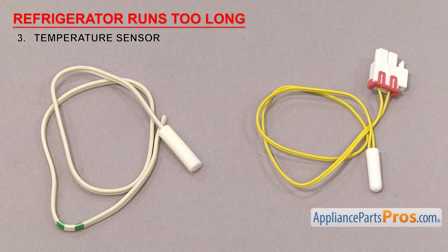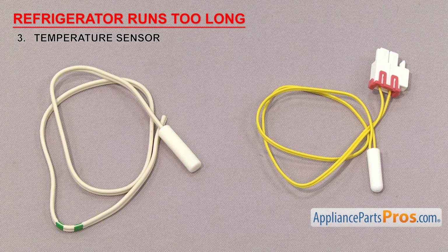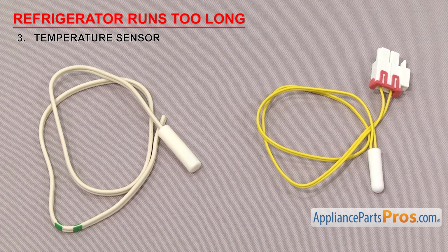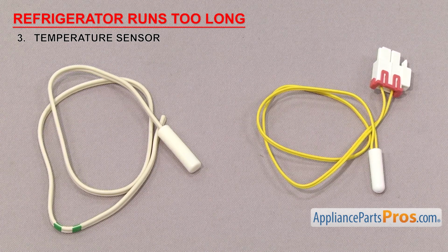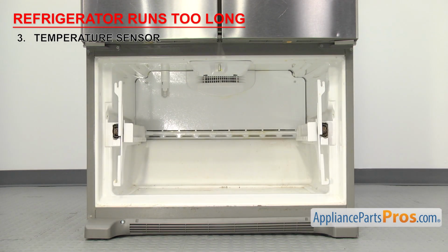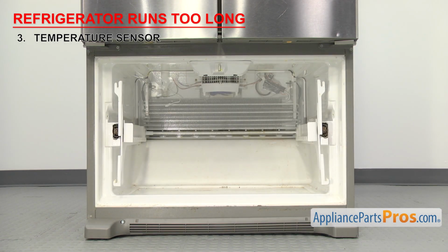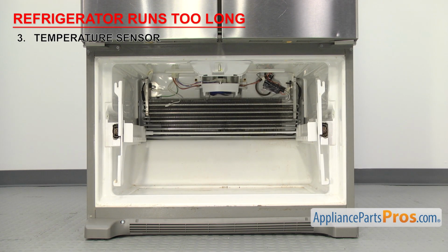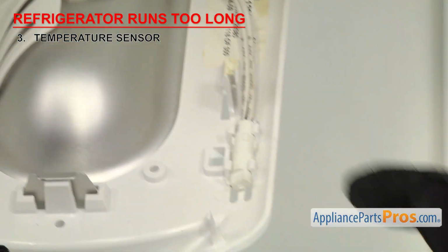Now we need to check the temperature sensor. It tells the control board the temperature inside the freezer. Temperature sensors are white plastic sensor bulbs. They tell the control board the temperature inside the freezer section so it can run the compressor as needed to maintain the desired temperature. Temperature sensors are often used in multiple places in the fridge, many times behind the back wall, inside an air duct, or behind an access panel.